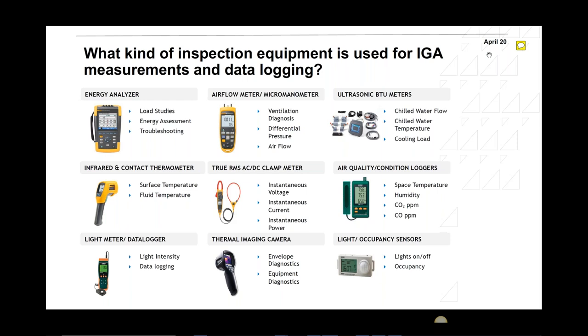Airflow meter, to check the flow on, let's say, an air handling unit. It can also show us the differential pressure, let's say, between the indoors and the outdoors. Ultrasonic flow meters coupled with temperature sensors on the supply and return for the chilled water on the chiller show us the BTU meter reading, or on the main header. Infrared contact thermometer: if something is very far and I need to take the temperature, I can use that. If something is very hot, let's say a boiler or an exposed pipe, I can use that to check the temperature. I can use a clamp meter to check the volts, current, and instantaneous power.